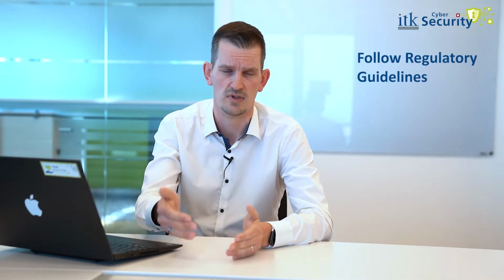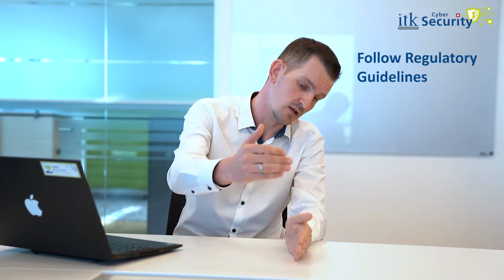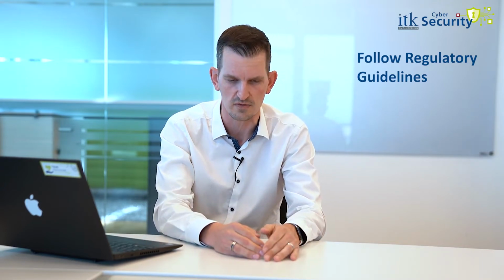If you want to go to the European market, however, we just said the guideline is far less specific. What you can do here is use cybersecurity checklists, like the one from the Johner Institute. The Johner Institute is a very trusted source for such checklists in the European market, and I will put a link in the video description so you can look it up if you are interested in this checklist. You take this checklist and go through the points, document what action you take because of some checklist points, and place this documentation into your medical documentation as part of your product.